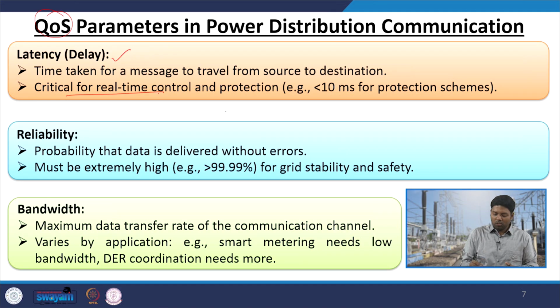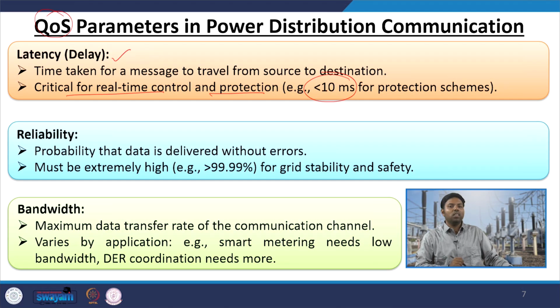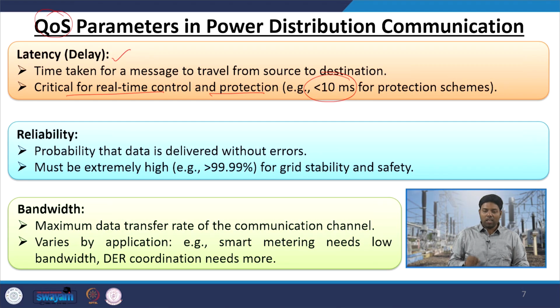For real-time control and protection, latency needs to be almost less than 10 milliseconds. For protection schemes, data from the farthest end, say a PMU, including the phasor and magnitude, has to reach the control center within 10 milliseconds to inform about the protection or fault condition.